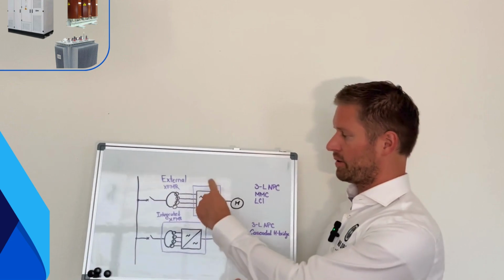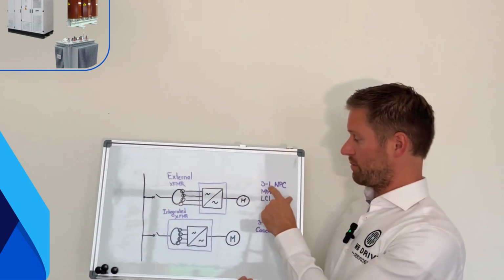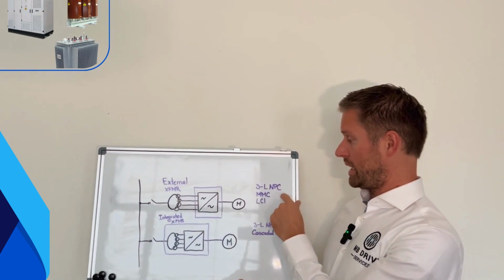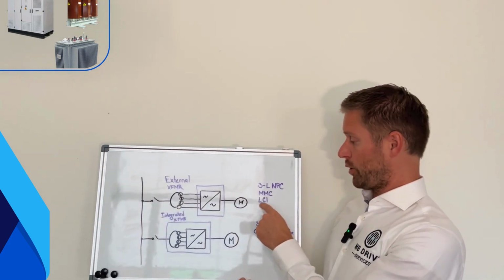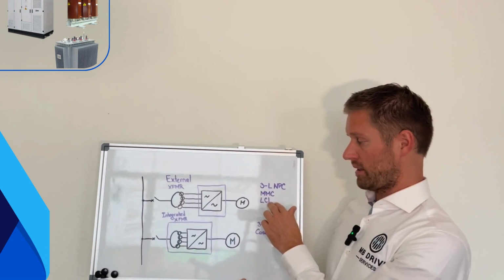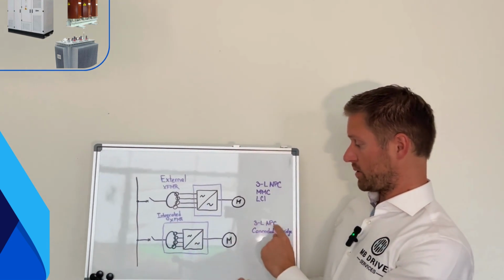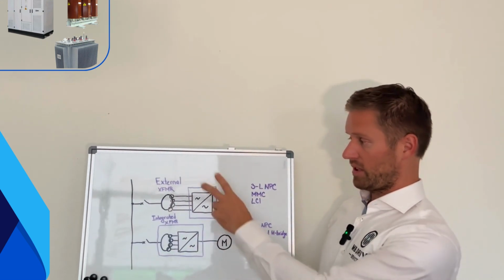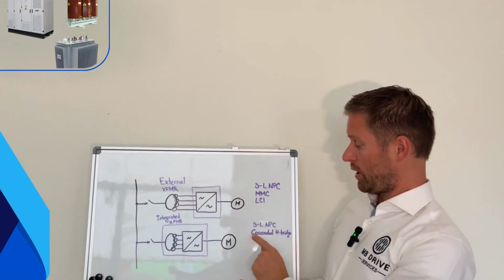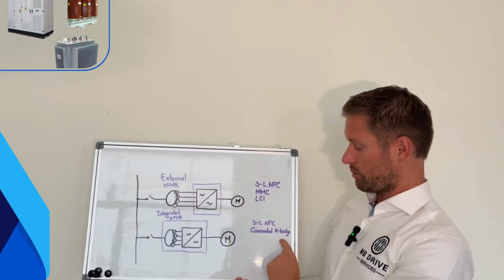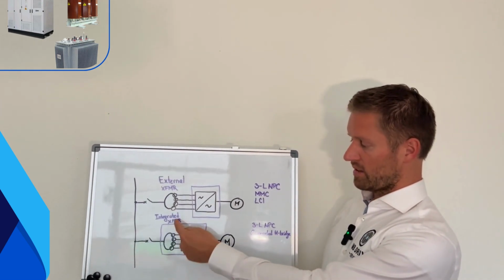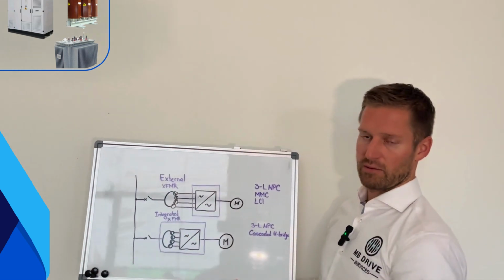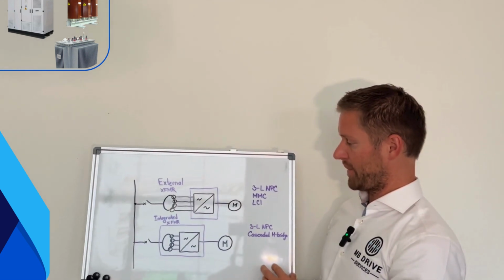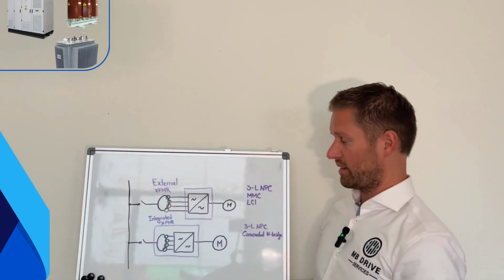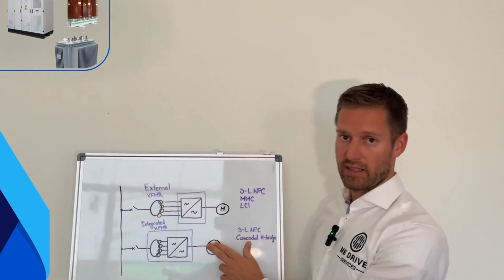Now just a few examples of what belongs where, what are some representatives. So the VFDs with the external transformer, this can be for example the 3-level NPC, neutral point clamp topology, or the modular multi-level converter, or from the current source the LCI, load commutated inverter. They come with external transformer. Integrated transformer, the same 3-level NPC, so that one can be available both with external or integrated transformer. And then a typical example that is only integrated transformer is the cascaded H-bridge. It's because there are so many secondary windings that to make the connections externally would be very complicated and troublesome. So these are some typical representatives of the VFDs with external transformer and with integrated one.